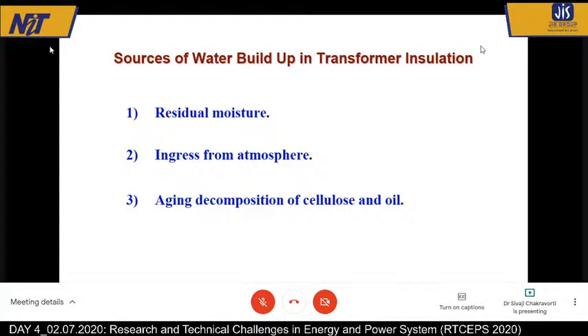But all this said and done, what will happen if moisture is generated within the transformer? Nothing can be done. And that is actually the primary concern, that due to aging, moisture is generated inside the transformer. And then that remains within the transformer and damages all insulation. So what we are today talking about is that part of the moisture which is generated as a part of aging.